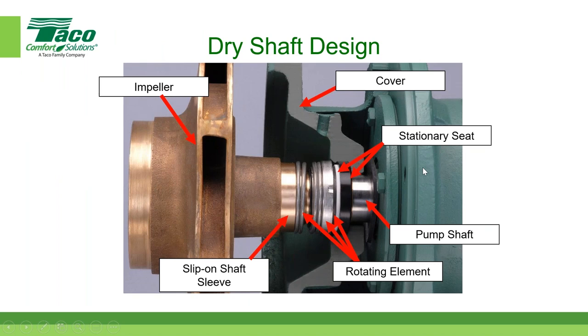And here's an even more blown up view of this. And really, this is for education, right? Maybe you get involved with taking pumps apart. There could be some contractors on here, or I know there's some reps that have taken pumps apart, or someone at their facility has. So there's the rotating elements of the seal. The pump shaft is tucked back here. That stationary seat actually sits right in here. So if you watch one of our videos, when they change the seal, you've got to pop that out. And there's the cover. That's mounted right here.